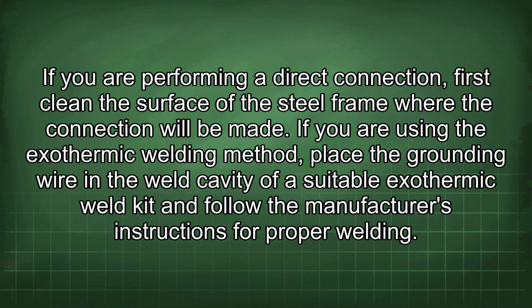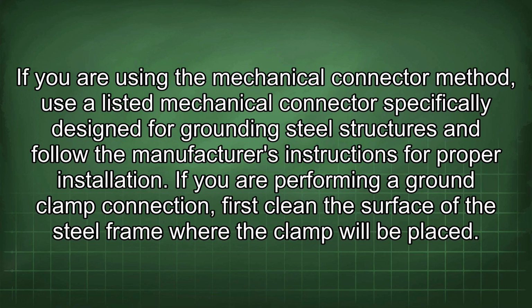If you are performing a direct connection, first clean the surface of the steel frame where the connection will be made. If you are using the exothermic welding method, place the grounding wire in the weld cavity of a suitable exothermic weld kit and follow the manufacturer's instructions for proper welding. If you are using the mechanical connector method, use a listed mechanical connector specifically designed for grounding steel structures and follow the manufacturer's instructions for proper installation.